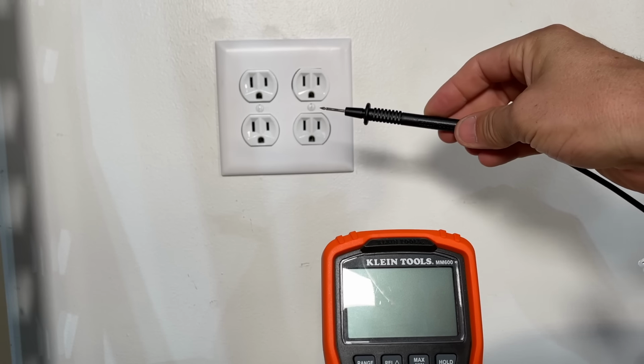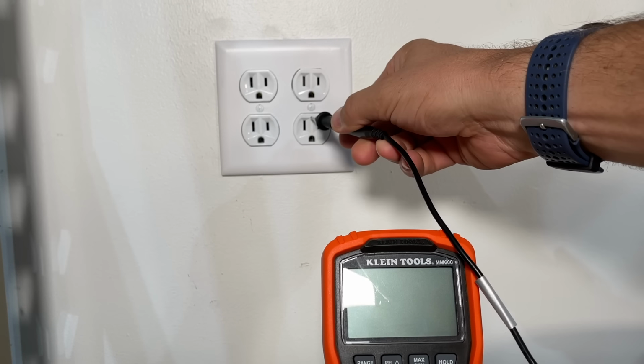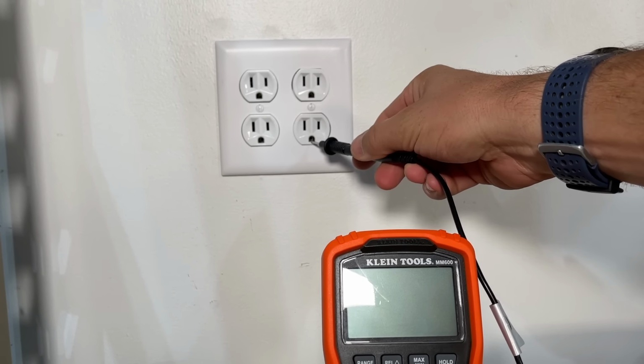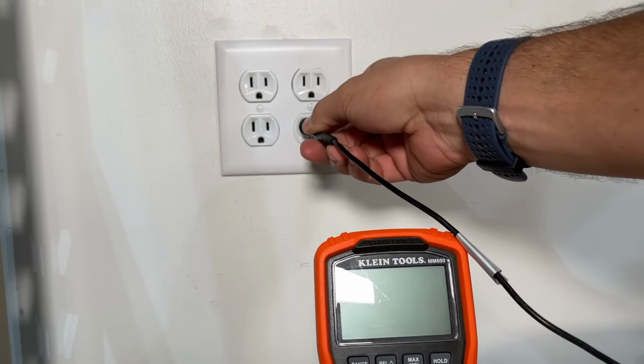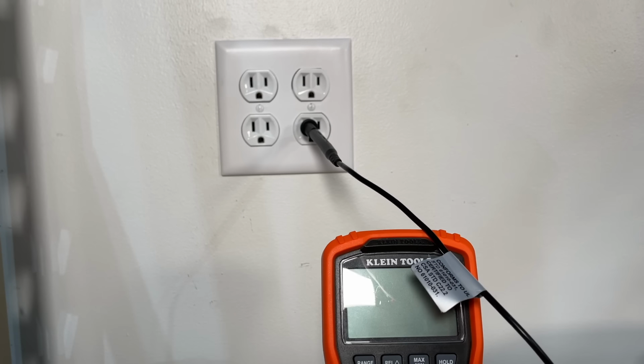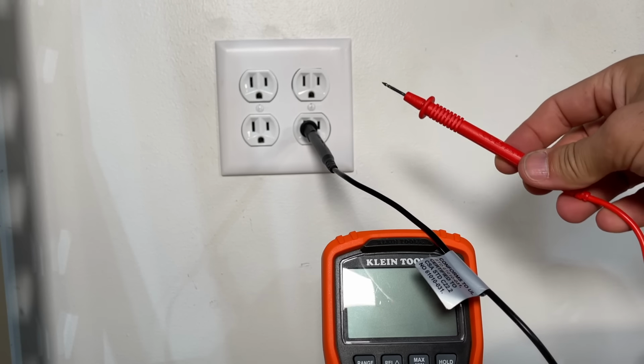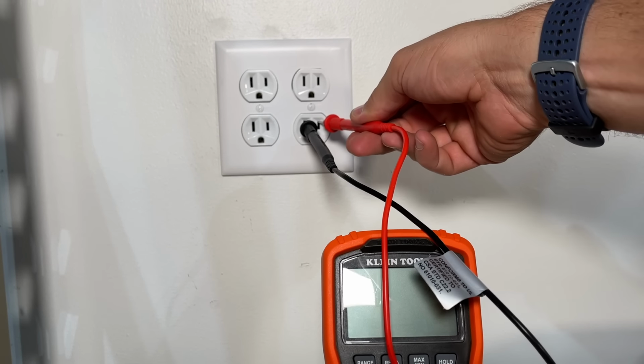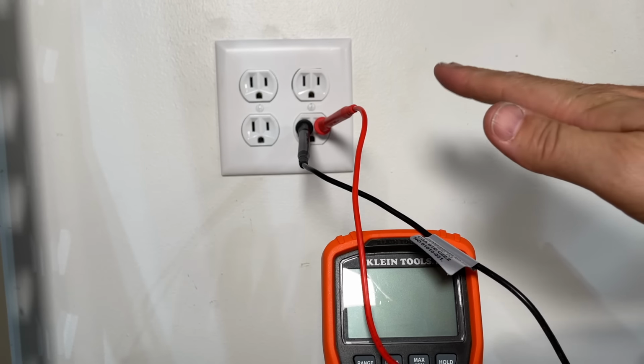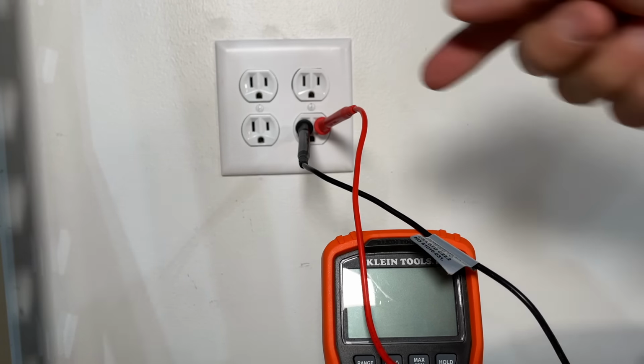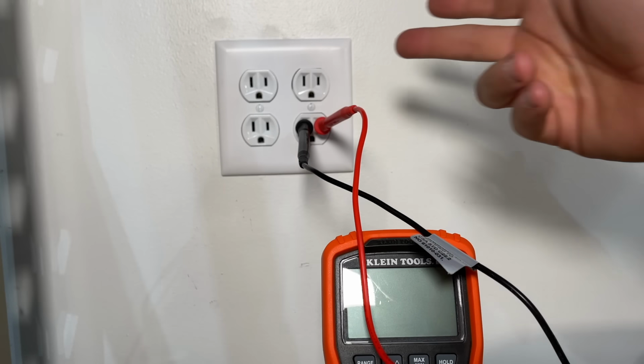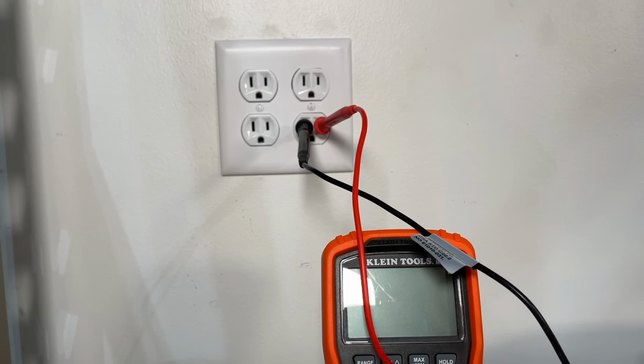You always want to start off with your black probe going into the neutral or ground side, depending on what you're measuring. Here I'll put it in the ground side. Then introduce your red probe into the hot side. You do not want to start off with the red probe, or take out the black probe while the red is still attached to the hot side.